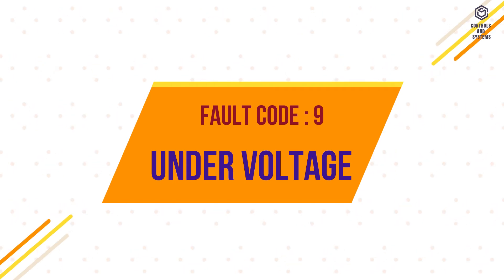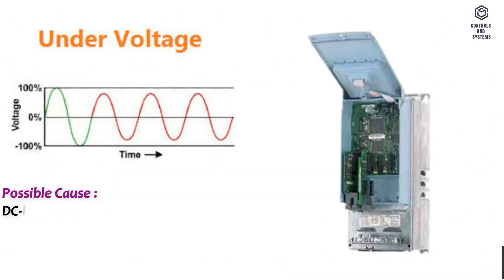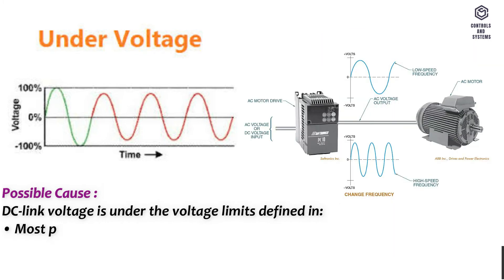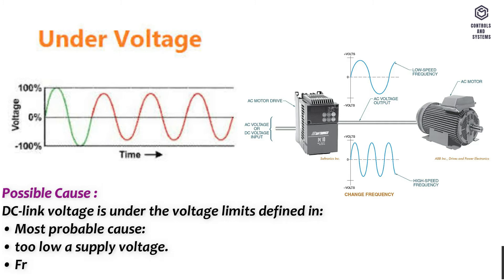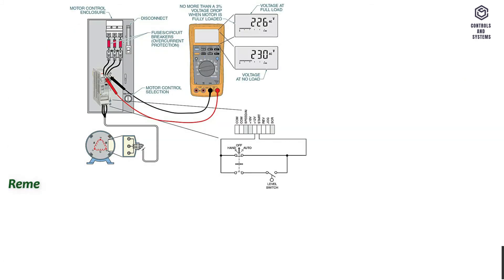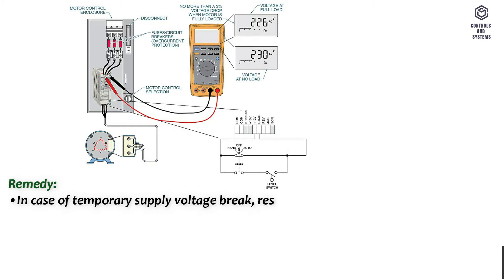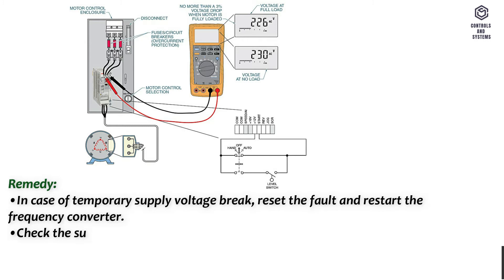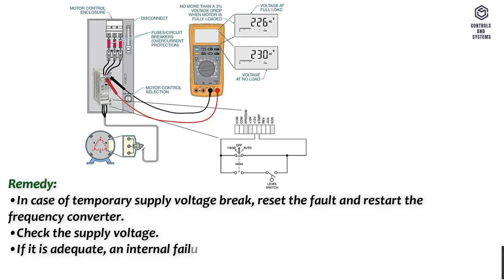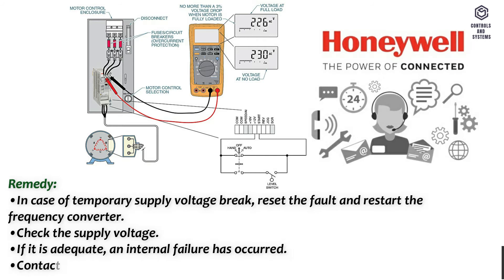Fault code 9 – Under voltage. Possible cause: DC link voltage is under the defined voltage limits. Most probable cause is too low a supply voltage or a frequency converter internal fault. Remedy: in case of temporary supply voltage break, reset the fault and restart the frequency converter. Check the supply voltage; if it is adequate, an internal failure has occurred — contact technical support.